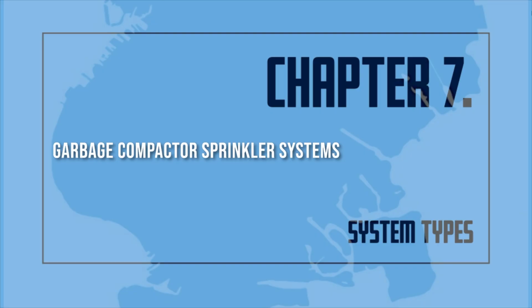If any minor defects in the system are discovered, they shall be reported to the owner of the building. If repairs are not made within 30 days, the certificate of fitness holder must notify the Bureau of Fire Prevention. If any major defects are discovered, they shall be reported to the FDNY dispatcher, the owner of the building, and the Bureau of Fire Prevention. Major defects shall be repaired immediately. When a fire is discovered in the compactor, the certificate of fitness holder should notify the local firehouse immediately and should not attempt to enter the compactor chute to put out the fire.